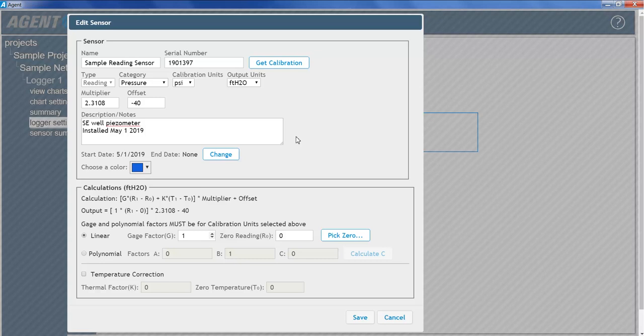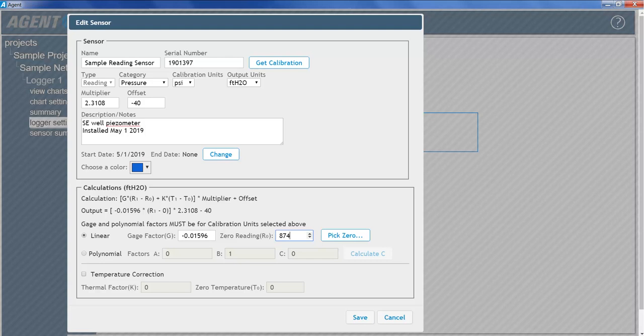Enter the linear gauge factor from the calibration report. Next, enter the vibrating wire sensor's initial on-site zero reading. If an initial zero reading has not already been established using a GK404 or similar readout, the sensor data collected by the logger can be used. To establish an initial zero reading using a GeoNet logger, click the Pick Zero button.